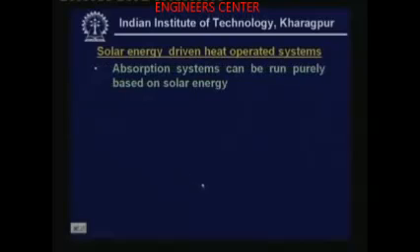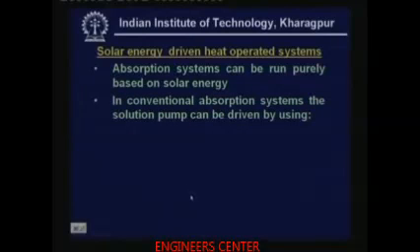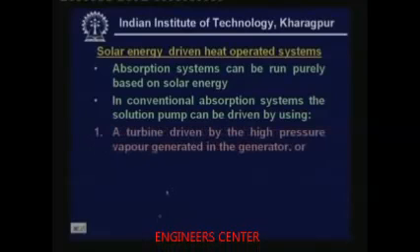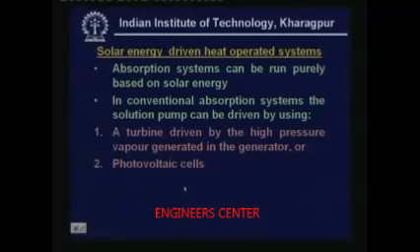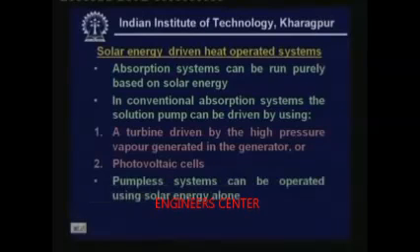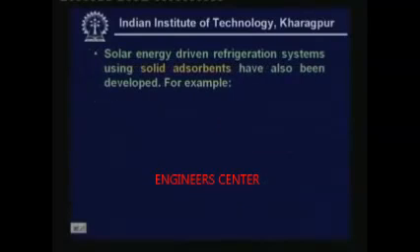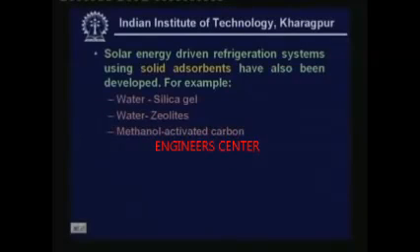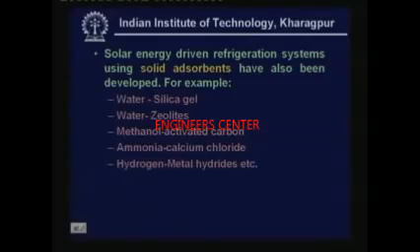Absorption systems can also be run purely on solar energy. For conventional systems, the solution pump can be driven by a turbine using high-pressure vapor from the generator, or photovoltaic cells can power a motor to run the pump. For pumpless systems, no mechanical energy is needed, so they can operate purely on solar energy. Solar-driven refrigeration systems can also use solid adsorbents such as water-silica gel, water-zeolite, methanol-activated carbon, ammonia-calcium chloride, and metal hydride systems, though these have not been commercialized on a large scale.